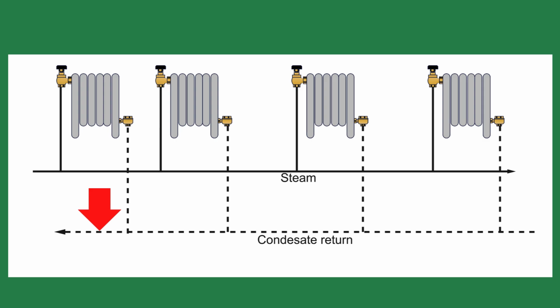This led me to the common condensate pipe on the floor below. Feeling the condensate pipes, they were cold. We flushed the horizontal condensate pipes and think we resolved the problem. We were not that lucky. The next day, the owner called and said the apartment was once again cold.